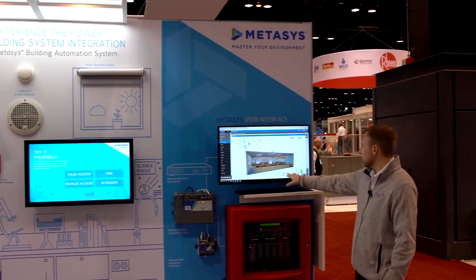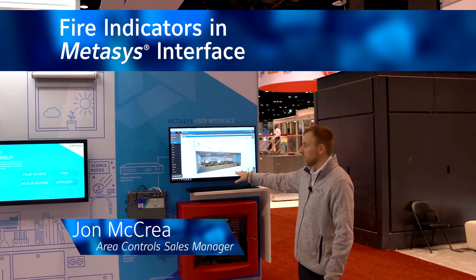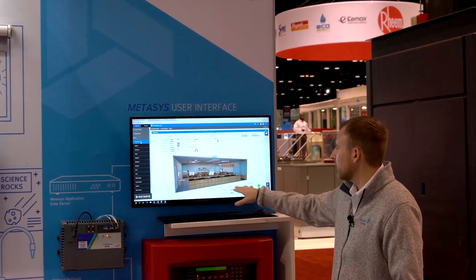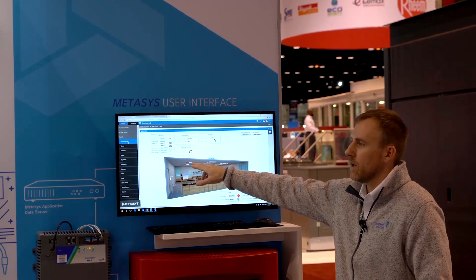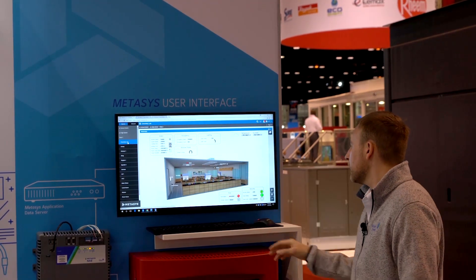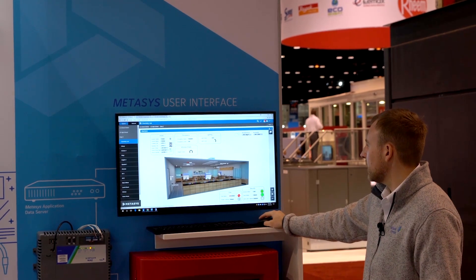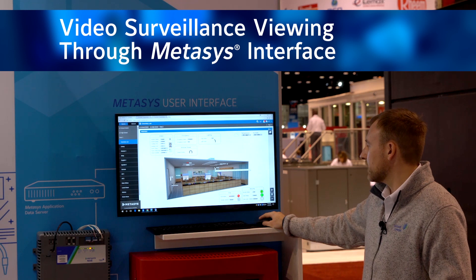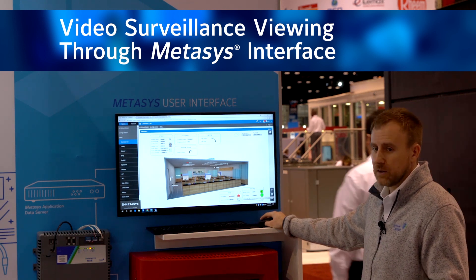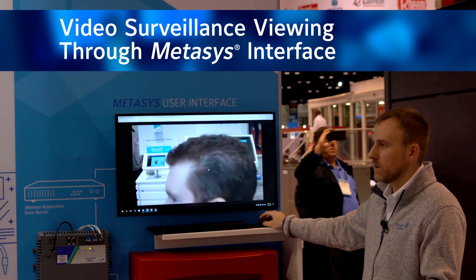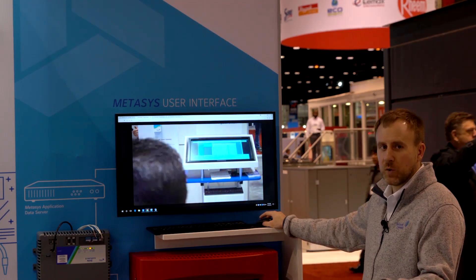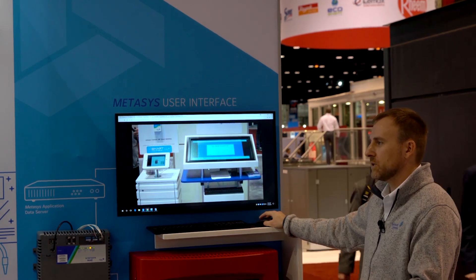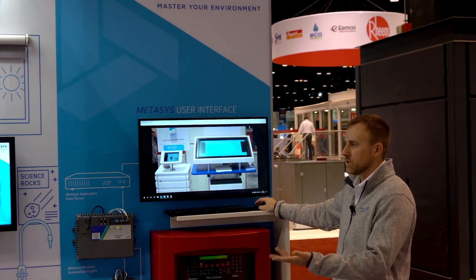What does the Metasys UI show? We can see that the pull station indicator has turned red, so we know right from there that there has been an event, and the strobe is also red up here in the graphic. Both of those indicators have happened, and the operator may also want to utilize the camera. They could click on the actual indicator itself and it'll take you right in to have a visual of what's going on in the chemistry lab — see if there's smoke, see what's actually happening, and have a more intelligent response.